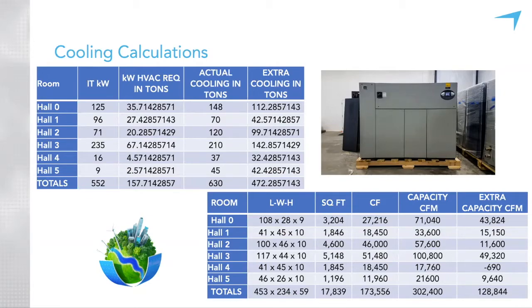But at Ohio State, our N+1 now is that we have two 20-ton CRAC units in standby. We have tested this over and over and over again. If one CRAC unit dies, it can call for the other to come up, or the other will see it. They stay in standby mode and will come up as needed. I've seen some data center folks with 24/7 staff who can very quickly walk in and flip one on. I can't tell you what is best for you, but here is a great way to size your cooling needs based on kilowatts.